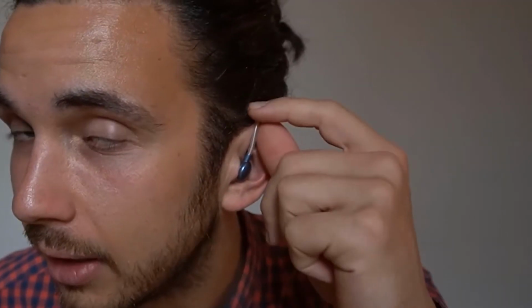Con number 3 is that neither you nor me can size the tubing here correctly. When I put this piece up and behind my ear, and then I put this piece in my ear, you can see here that the tubing length, it's too long. I would love for that tubing length to be shorter so I could actually fit it more appropriately on my ear. It would look better, it would be more comfortable. But because inside of the tubing there's an electrical wire, you can't adjust or cut the tubing. That's a big problem and probably will lead to this not being comfortable on your ear.